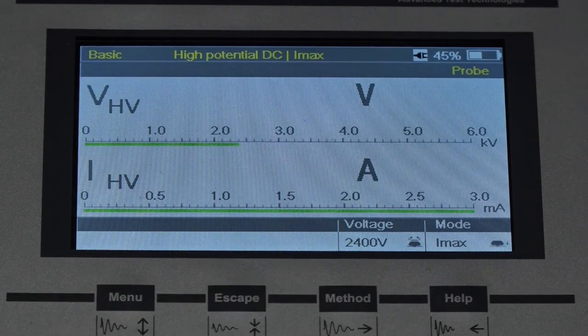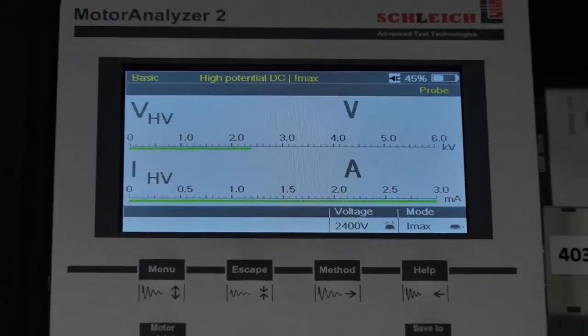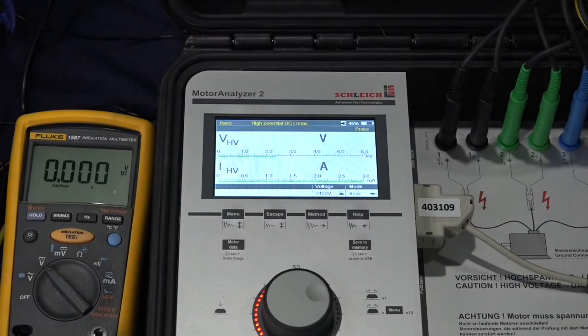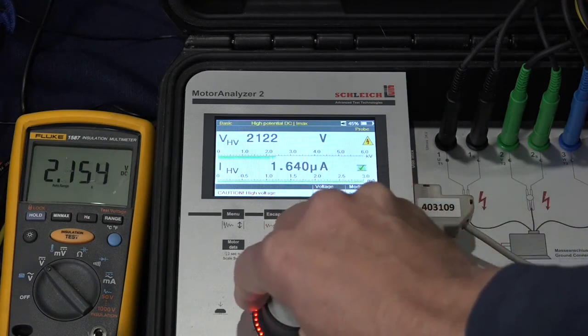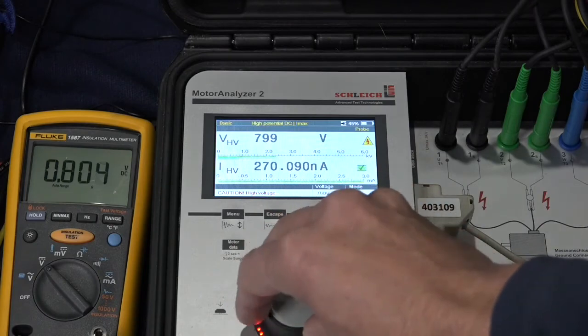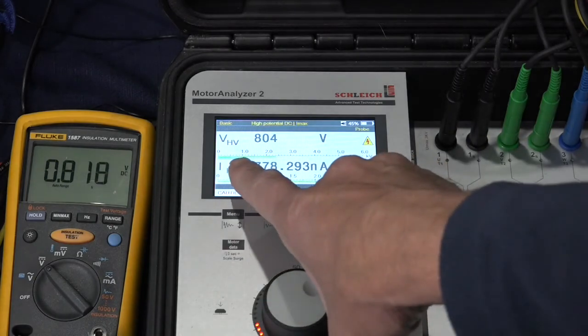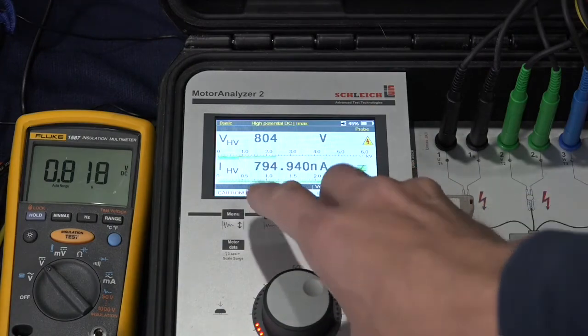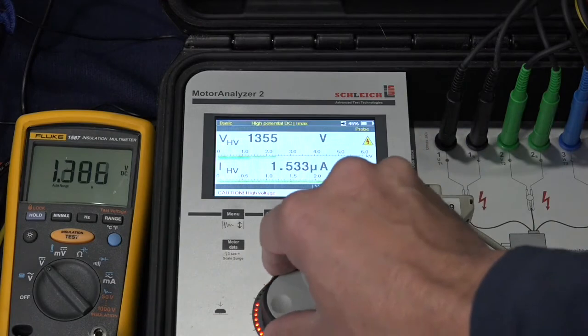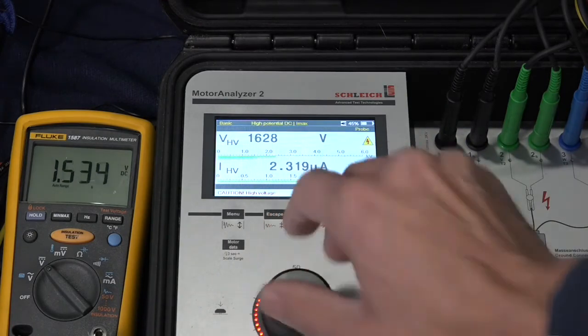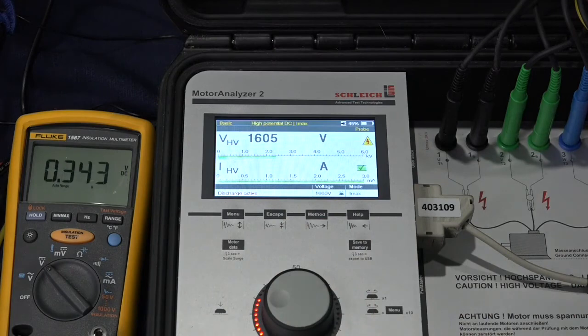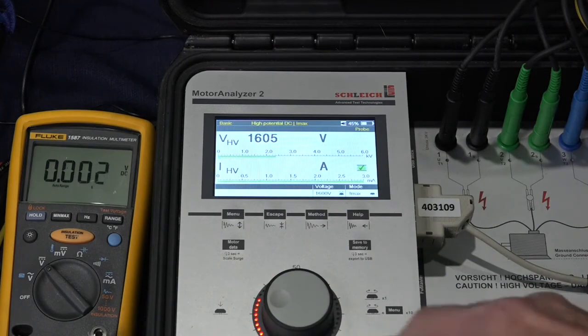So I'm going to back out so you can see the display of the DVM, and we'll run the test. Now you can see it automatically went up to the 2400 volts that was programmed, but you can also change the voltage with the control wheel or the whiz wheel. So you can see here on the display there's a little bar underneath another green bar for the voltage display, and that goes up and down as you bring the voltage up and down. I'll stop this. Now you can see there that it discharged the ground wall capacitance, and we're back to where we started.